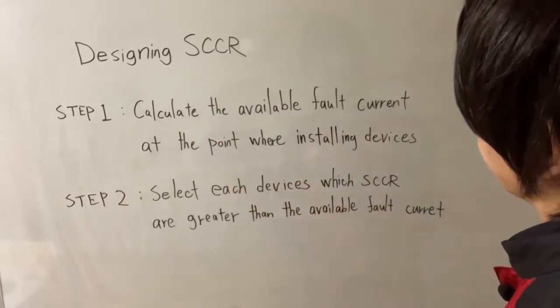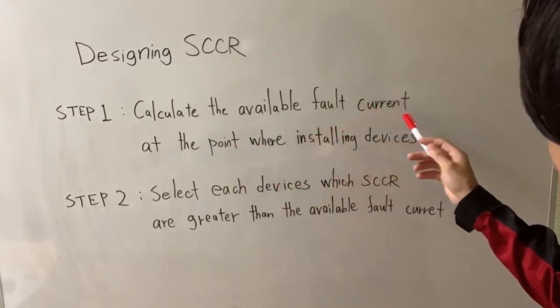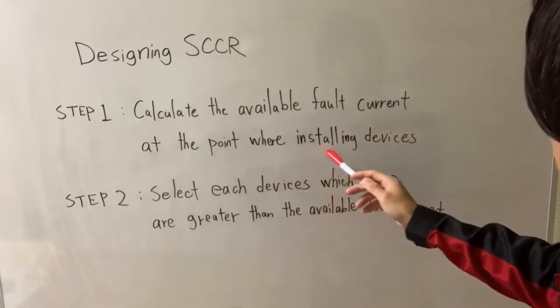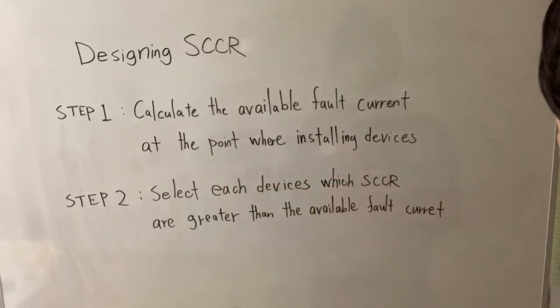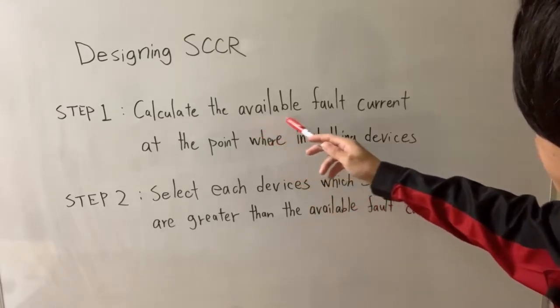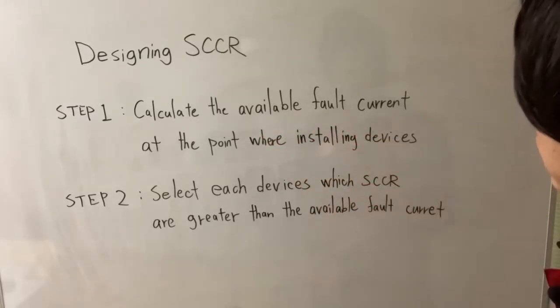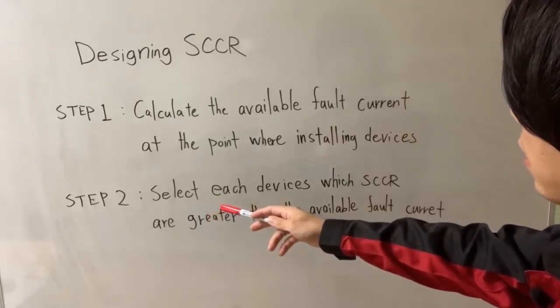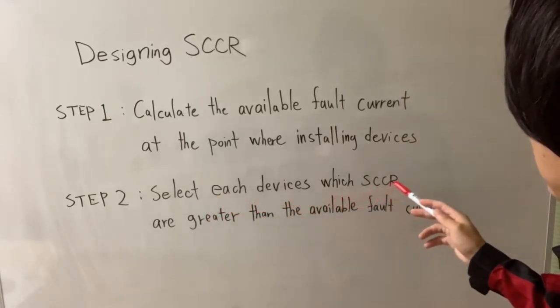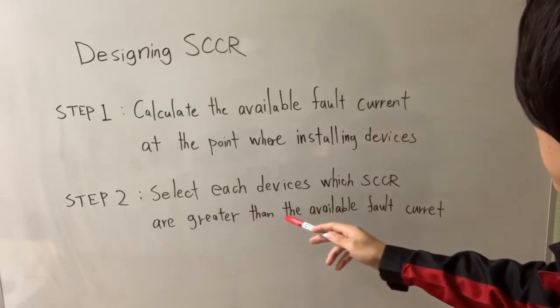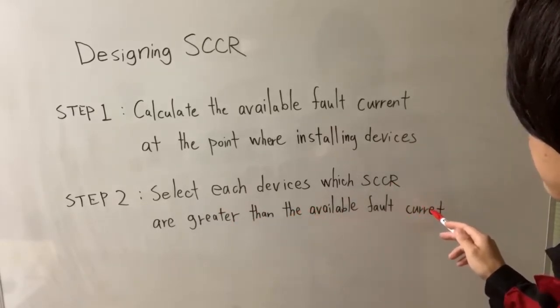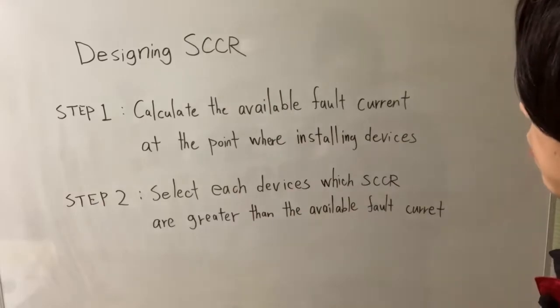Step 1: Calculate the available fault current at the point where installing devices. And in most of the cases, the maximum available fault current is a three-phase short circuit. And step 2: Select each device which SCCR greater than the available fault current that derived in step 1.